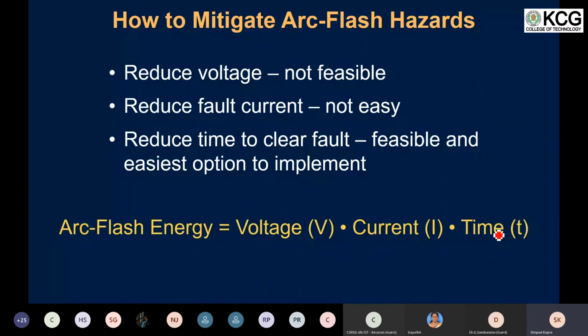If you look at the current, there are a couple of ways to reduce it. It may be by increasing the impedance of the incoming transformer, or by reducing the ground fault current by implementing a high resistance grounded system. In any of these cases, the hazards related to arc flash are limited to some extent, but from the economic point of view, it is really difficult for an industry or a power generation company to implement this kind of system. The other way of reducing the arc flash energy is by reducing the time, and this turns out to be the most economical way to limit the arc flash energy.